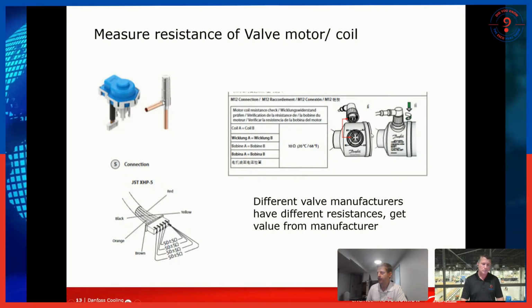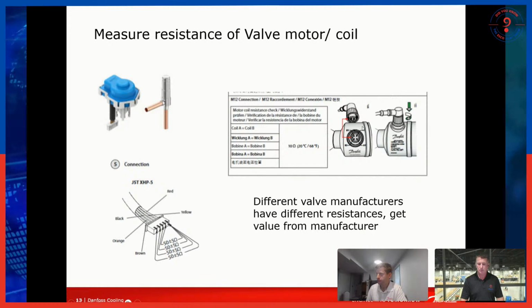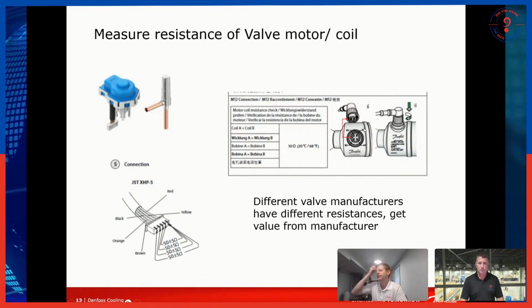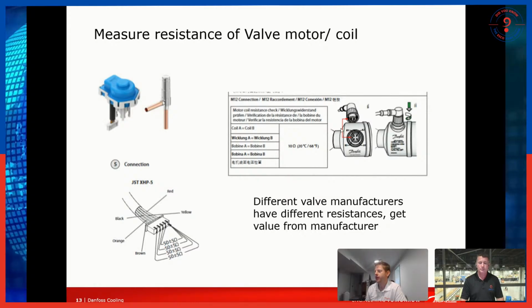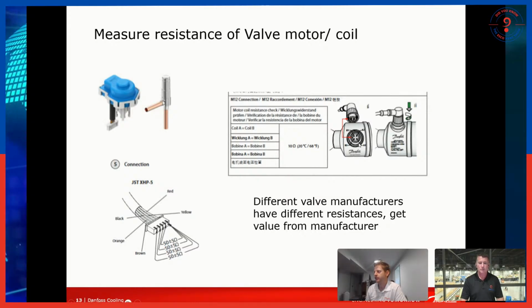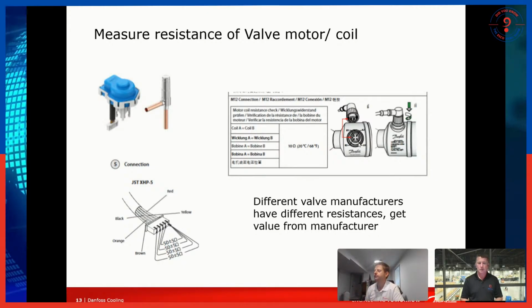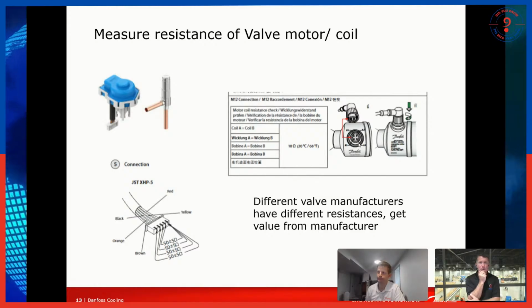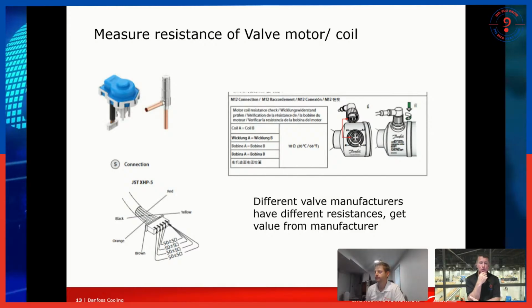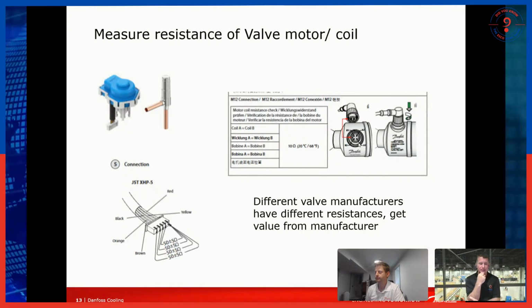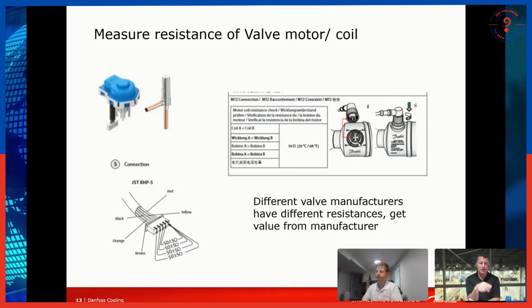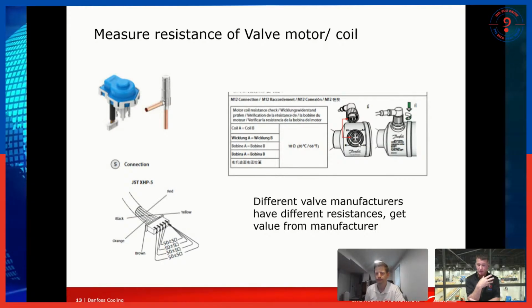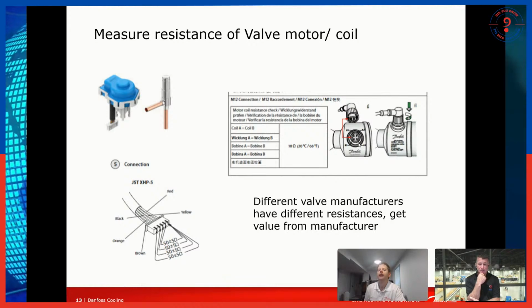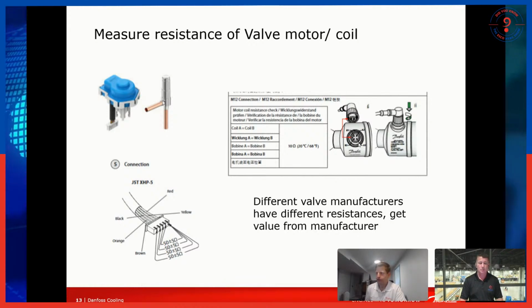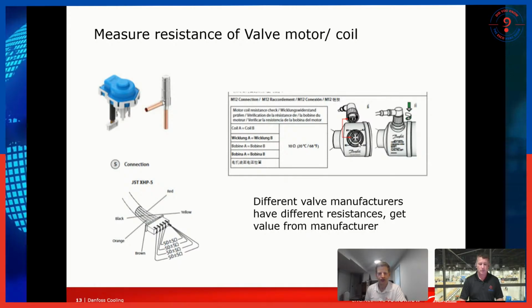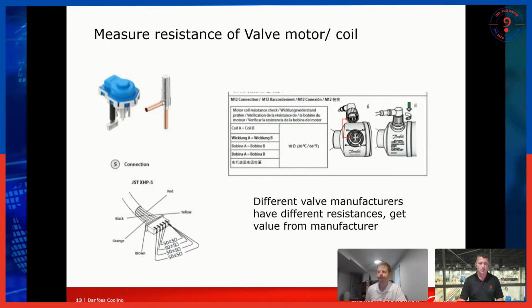And the same thing happens with the bipolar stepper motors. But there you are measuring the resistance between the A's and the B's. You're measuring it across certain points. So that's a really good slide, because I've been looking for what tolerance is acceptable on our resistance reading for our windings, and I see that you have a plus or minus 5. So we're looking for a plus or minus 10% as an acceptable range then within our resistance readings. Yep, that's the number that I see for most Danfoss EXVs. I don't want to make promises for other manufacturers, but 10% is usually a pretty good rule of thumb.